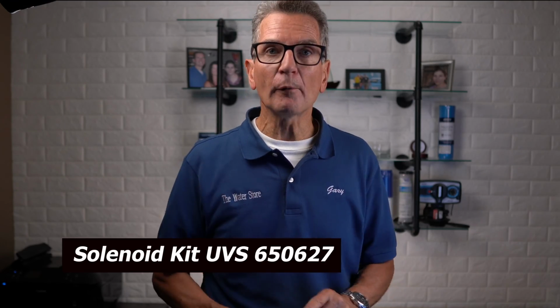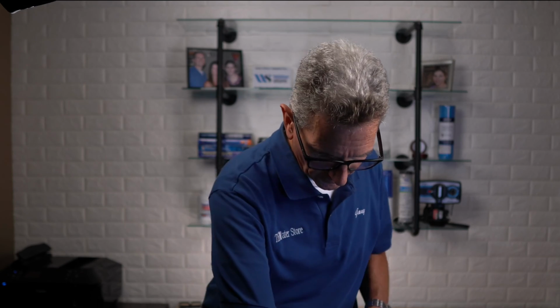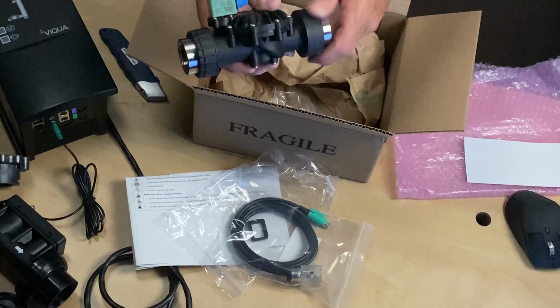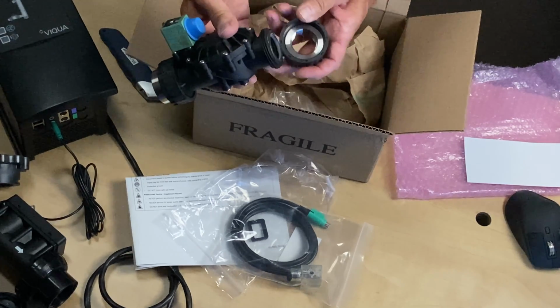The third thing you need is a solenoid. So a solenoid is optional in these systems, but we've got one here. So let's have a look at that. So again, it comes with the cable, it's color coded, so it plugs right into the controller in the right spot. And then you can see this is the solenoid here by itself. And you can see that it's quite well built. And what I like about these, it has these pretty much quick connect type of fittings that you can just unscrew and replace this, because the solenoid won't last forever. And again, for a light commercial or a home where you're putting one of these systems in, I definitely suggest you have a spare solenoid on hand, because if something goes wrong with the solenoid and it shuts off your water flow, and you have to order that replacement solenoid, it might take a while. So having one on hand means that you can just swap it out.